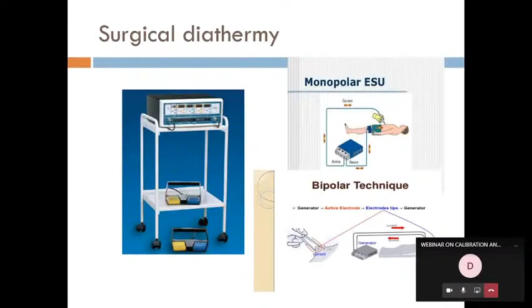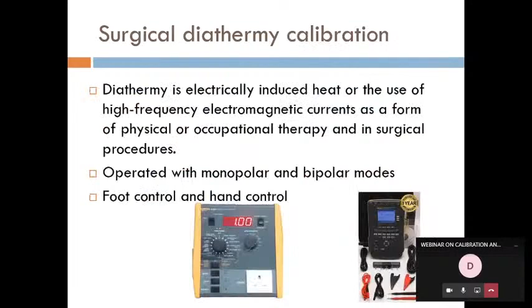What can you calibrate with this machine? You can test it with the help of an electrical safety analyzer. With the analyzer, you can measure any leakage current available: earth leakage, enclosure leakage, insulation leakage, everything. Only the safety test is available for the surgical diathermy. Everything can be checked with the help of the electrical safety test.